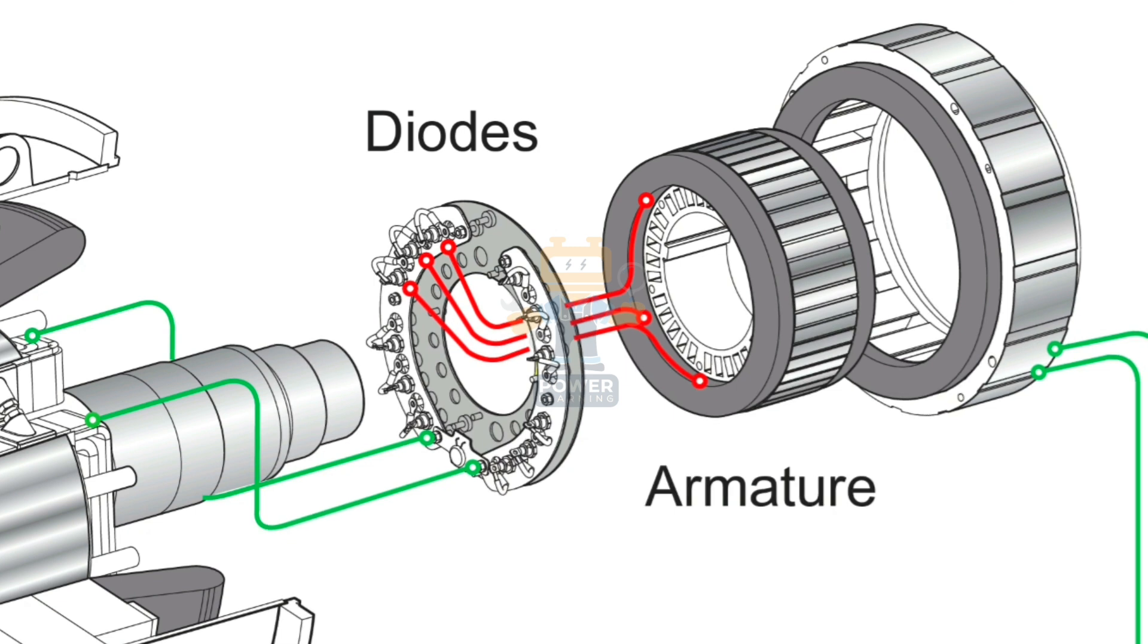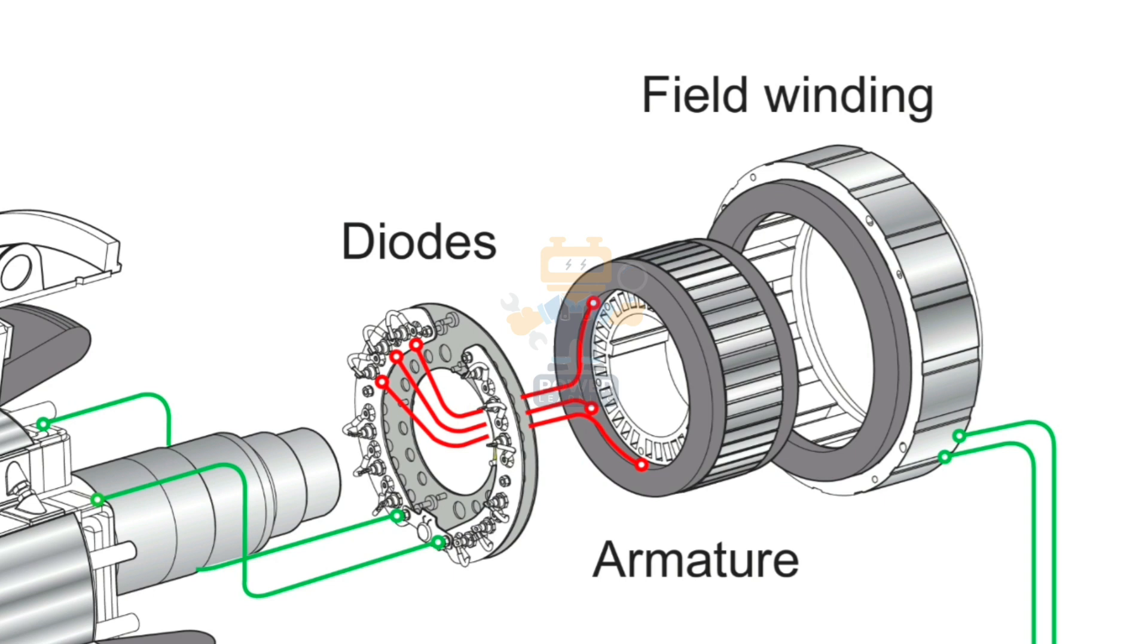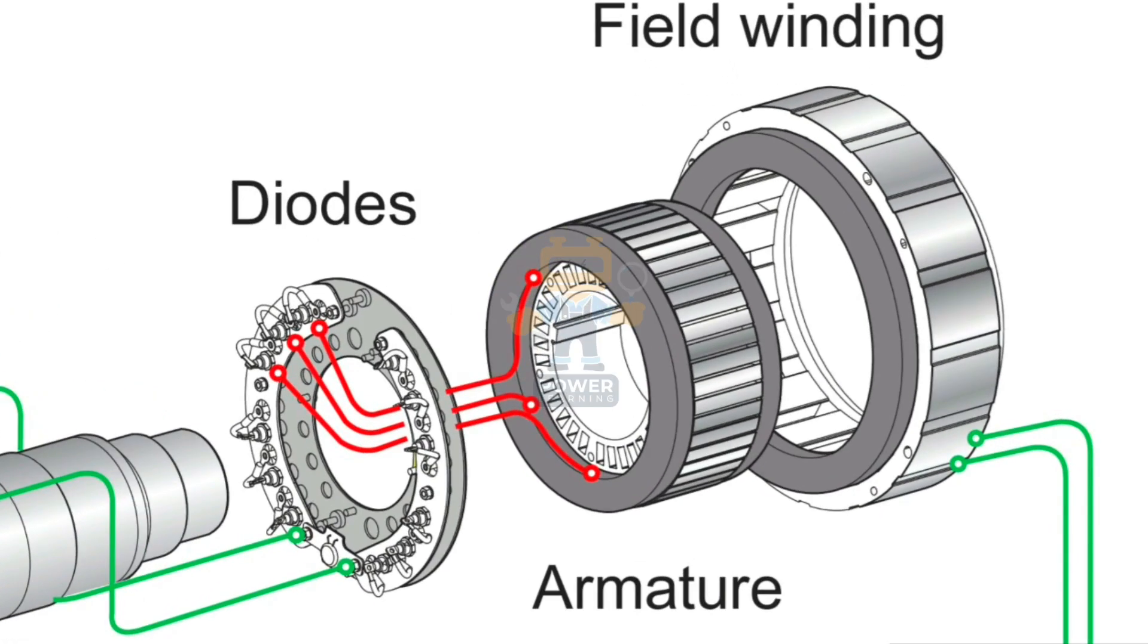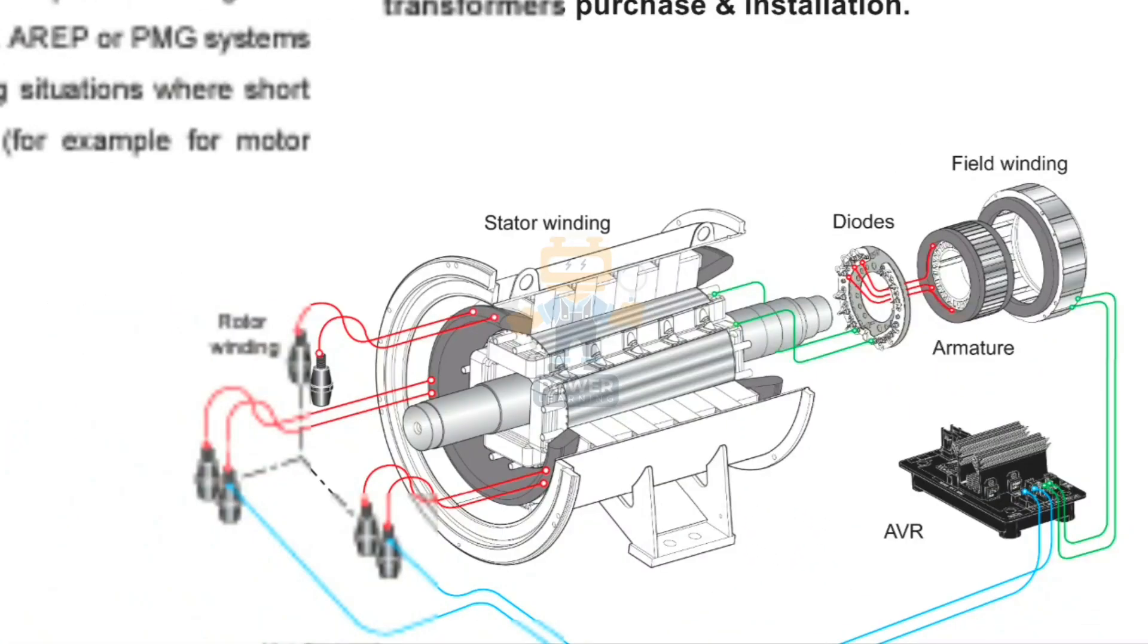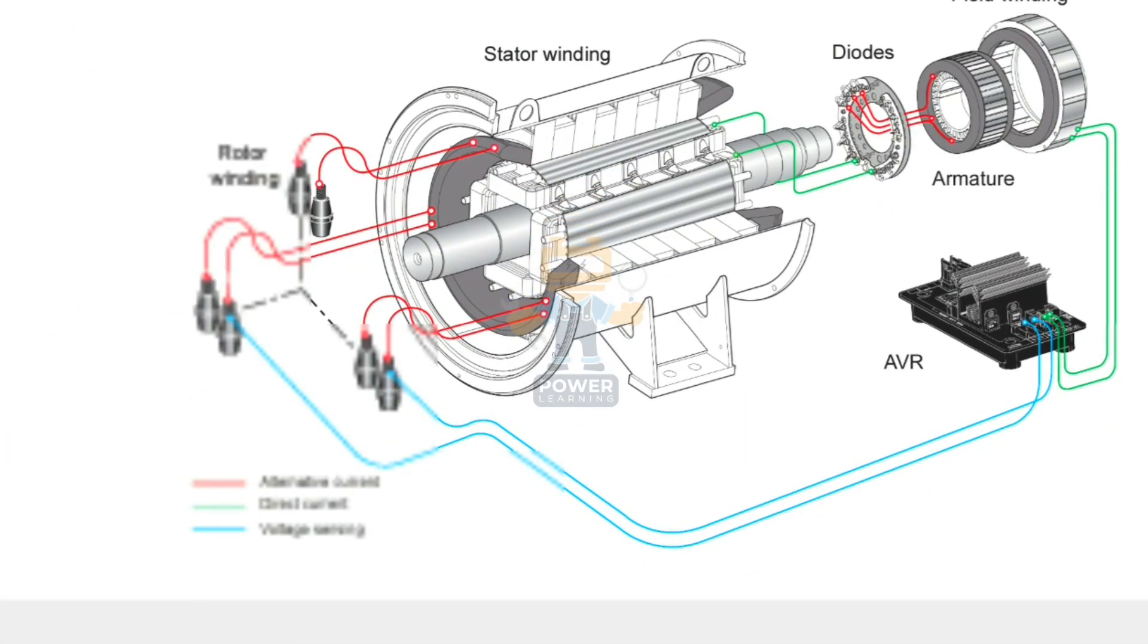This three-phase AC power we take from armature and give to our rotating diodes. These two parts, armature and diodes, are installed on the main shaft of the rotor, so they are always revolving with the engine, while our exciter field winding is stationary - not revolving.